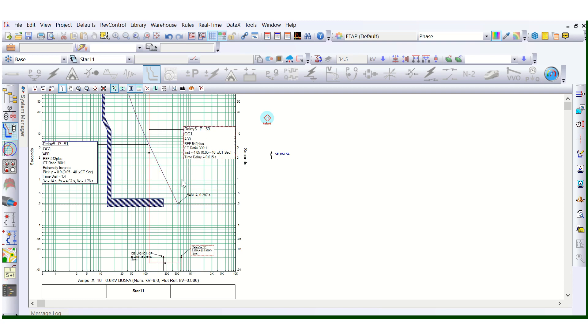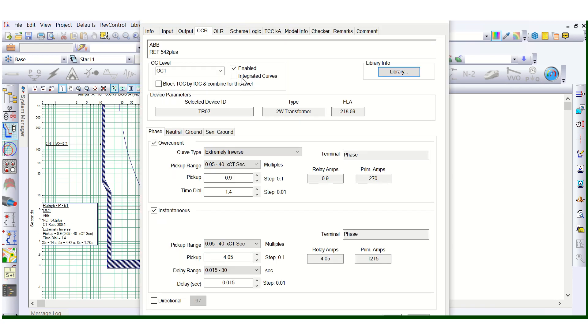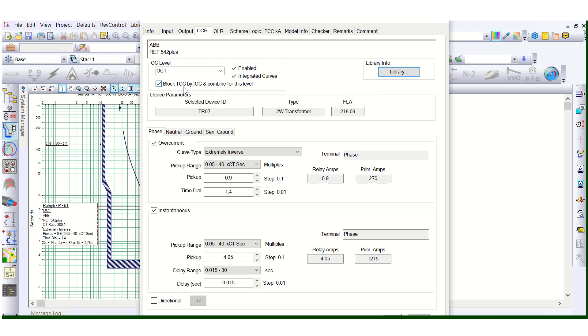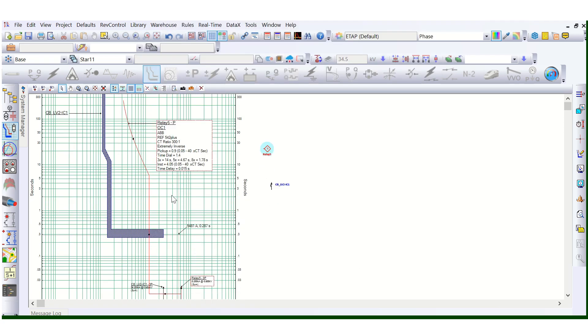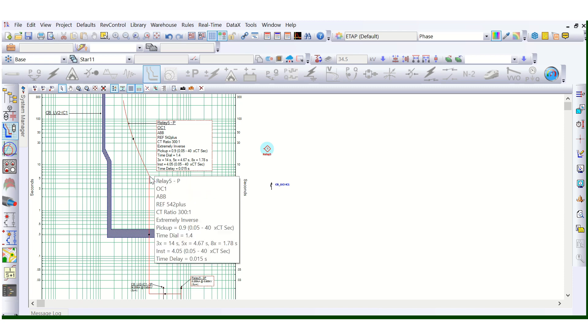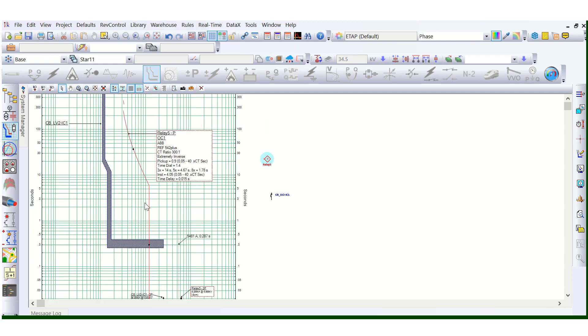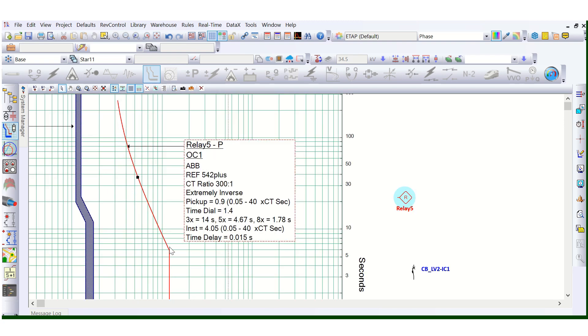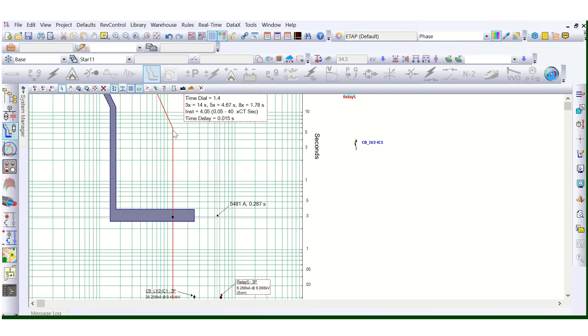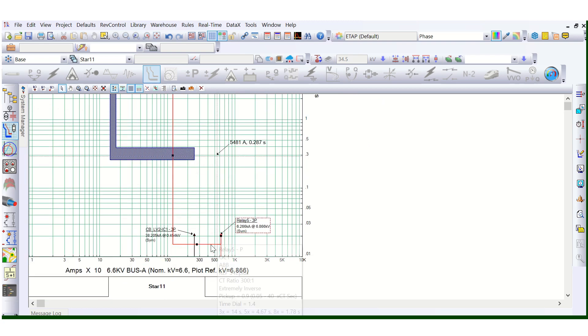This is 51 and this is 50. When using the integrated curve — Block TOC by IOC and combine — it will be shown as an integrated curve. Block TOC means block time overcurrent (51) by instantaneous overcurrent (50). If I enable this, you can see the integrated curve: at this point the 51 is blocked by the 50. So this portion is 51 and from this point onward this is 50 — the instantaneous setting.